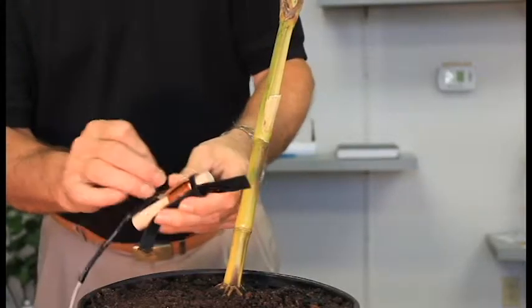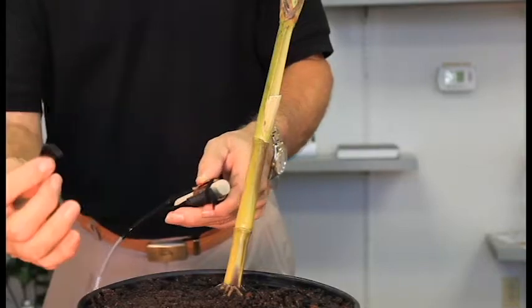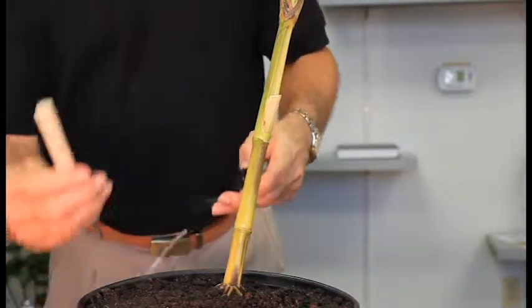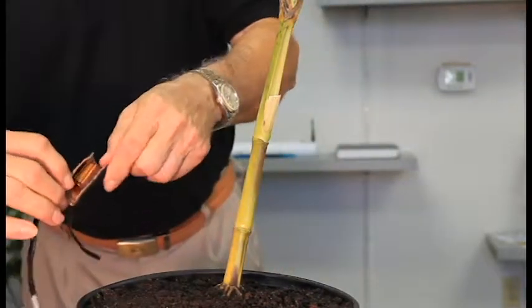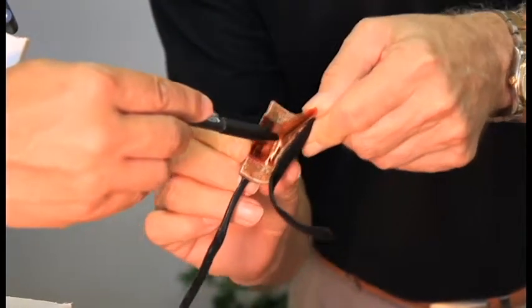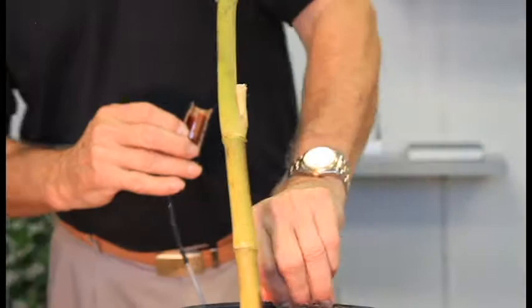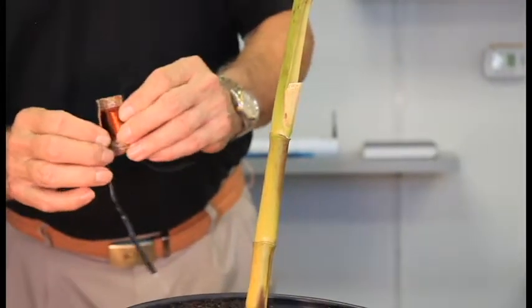This is the SGEX16 sensor and it comes with some wrappings to hold it in place. These are not used for the installation, so I'll simply take those off and put them aside, and then take the dowel that's used to keep its shape. I'll show you the upper and bottom part. There are thermocouples above — there are two there and two on the bottom. These both need to be in a very secure position on the plant. There is a notch here and I don't want to put it on that notch. I will put it on the flat side of the stem, and then the heater needs to go all the way around.